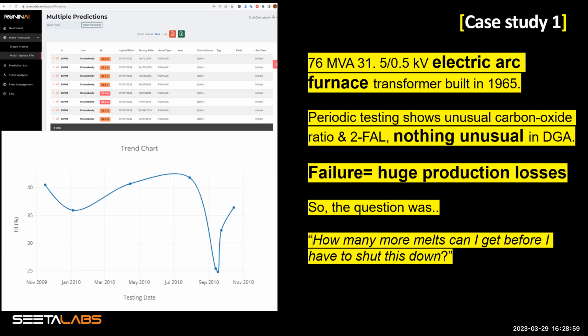Which means if I tell you that the health index of your transformer near the end of 2009 was about 40%, it means that for an electric arc furnace transformer, it was performing well. And eventually in January, somewhere in January 2010, it started dropping, which is natural degradation, looking at the number of all the information that you have given.